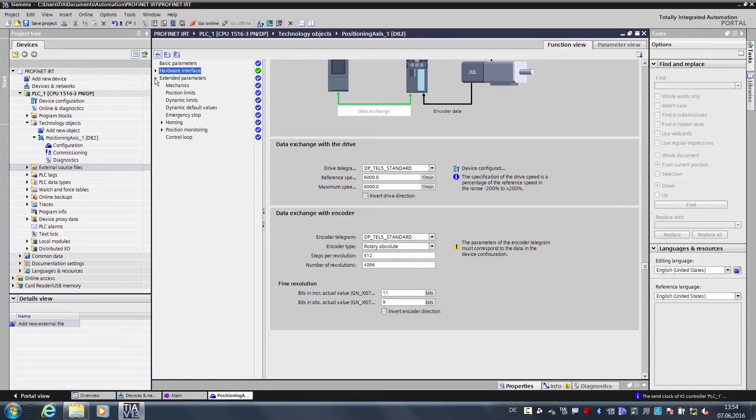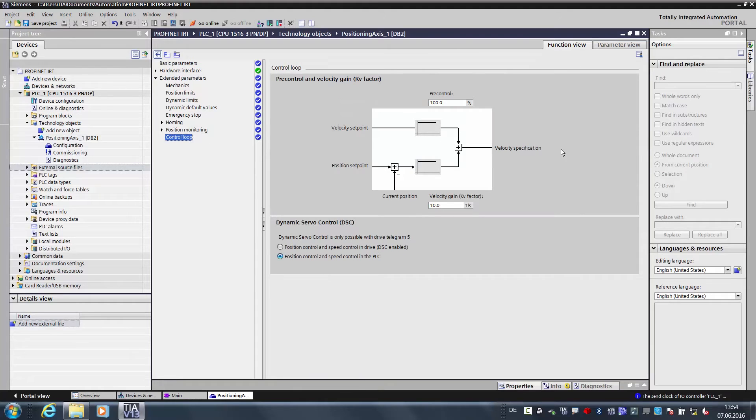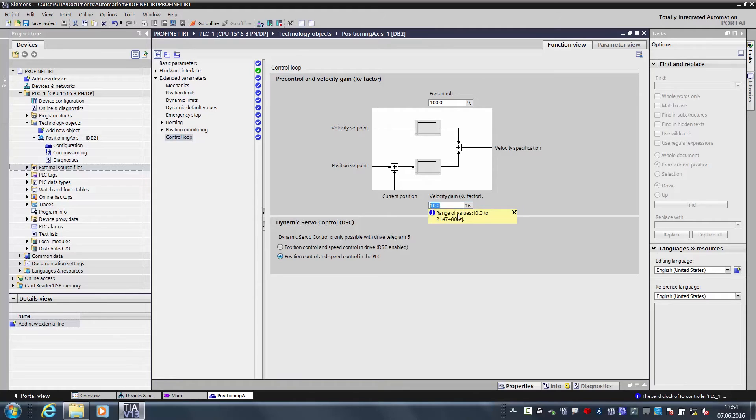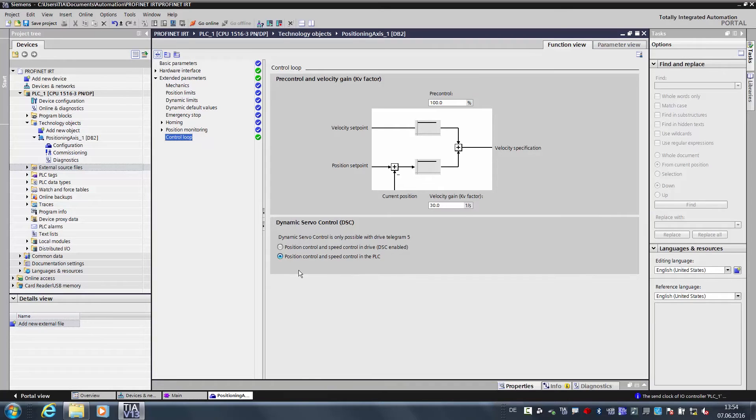Now we move on to the extended parameters and examine the controller. We keep the pre-control at 100%. We increase the KV factor from 10 to 30 so that the axis is somewhat more dynamic, and we also activate the dynamic servo control. By means of dynamic servo control, DSC, we divide up the controller somewhat. First, there is the target value generation that remains in the controller and is calculated at a cycle of one millisecond for example. In addition, we use the fast controller for 125 microseconds in the drive, and as a result, we can more quickly compensate for disturbances.